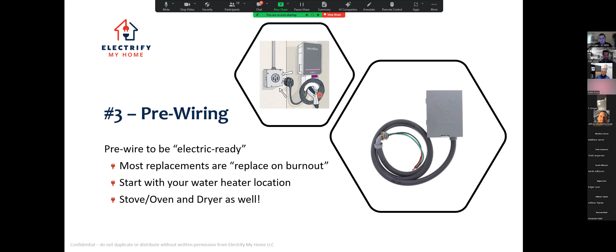Pacific Gas and Electric takes a long time to get panel upgrade approvals in some applications. So we'll install a simple switch in the house that runs, say, the stove circuit, and then rob off that stove circuit to run our heat pumps. Anytime the stove isn't running, the heat pumps will run. We think a couple of these installs will only be a problem on Thanksgiving Day if they're cooking for the whole family—the heat pump won't run while the stove's on all day. But usually stoves aren't on for the whole day.